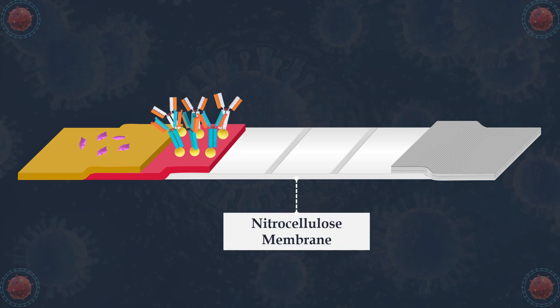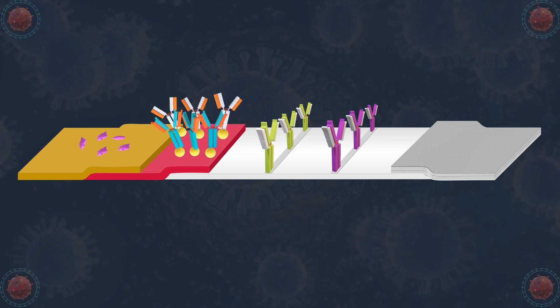The test strip also contains a nitrocellulose membrane with two lines: the first line coated with monoclonal anti-SARS-CoV-2 antibodies, and the second line coated with mouse monoclonal anti-chicken IgY antibodies. In addition, an absorption pad is used in the test device to move the sample across the test strip.